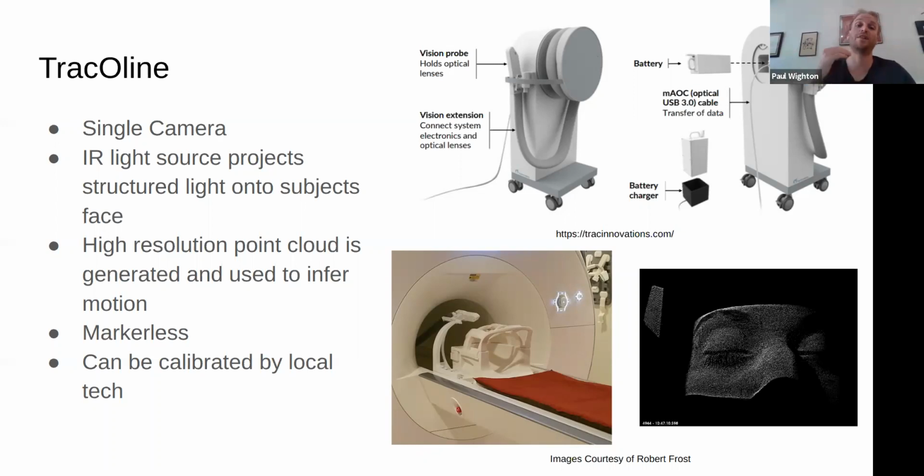That's the motivation for prospective motion correction. There are a lot of tricks you can do to back out what k-space might have looked like there, but it'll never be as good as the acquisition. GRAPPA and SENSE, especially since it's done in image space, are especially motion sensitive. If you're using an approach where you can dump acquisitions and get rid of them, that's fine.